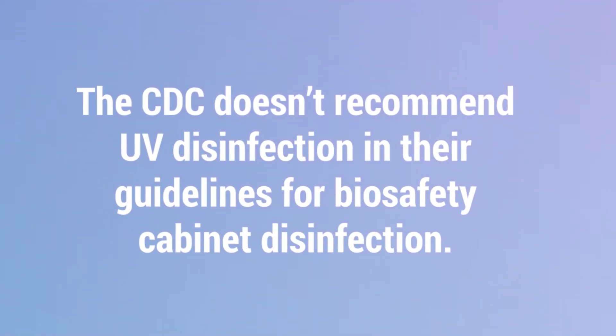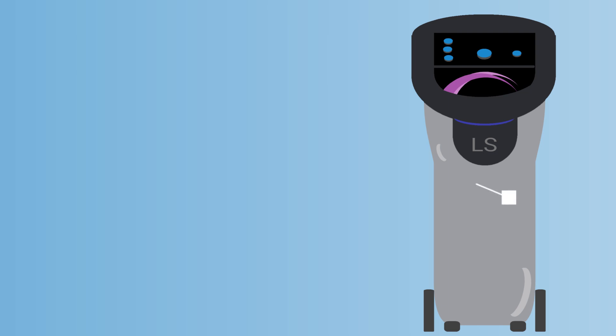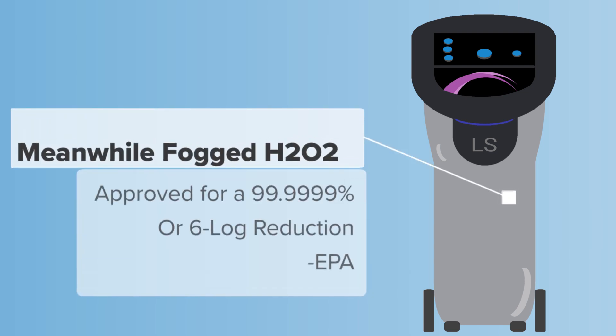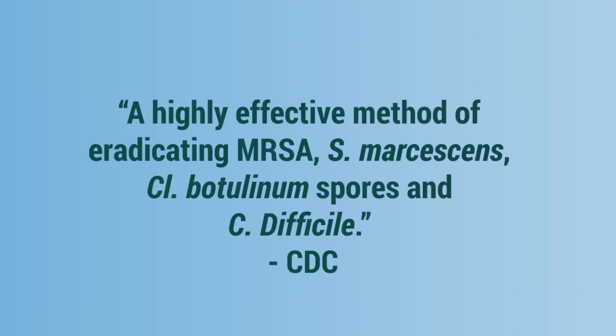Meanwhile, fogged hydrogen peroxide has been approved by the EPA for a 6 log kill, or 99.9999% reduction, and the CDC has said that hydrogen peroxide vapor decontamination has been found to be a highly effective method of eradicating MRSA, Clostridium botulinum, and Clostridium difficile. This point clearly goes to dry fogged hydrogen peroxide.